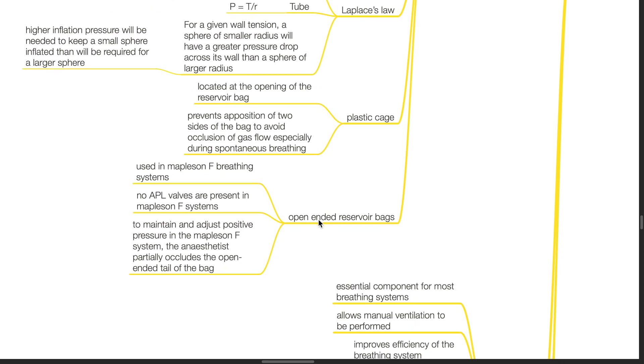Regarding open-ended reservoir bags, these are used in Mapleson F breathing systems. No APL valves are present in Mapleson F systems. To maintain and adjust positive pressure in the Mapleson F system, the anesthetist partially occludes the open-ended tail of the bag.